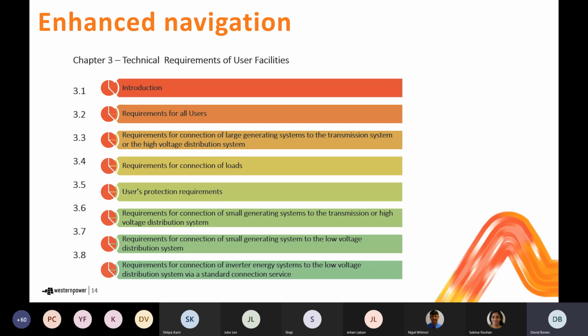We then step into section 3.2, which specifies the requirements that are common to all users. 3.3, which we'll spend a fair bit of time discussing today, presents the requirements for large generating systems. And those requirements apply to large generating systems, whether they're transmission connected or distribution connected. And by large generating systems, we're really meaning generating systems that have an aggregate capacity of greater than 5 MVA. We then in section 3.4 talk about the connection requirements for loads. And in 3.5, we've drawn together all of the protection requirements into one place. And you'll see within 3.5, there are some subsections separating out different arrangements for different users. I'll go into that on the subsequent slides.